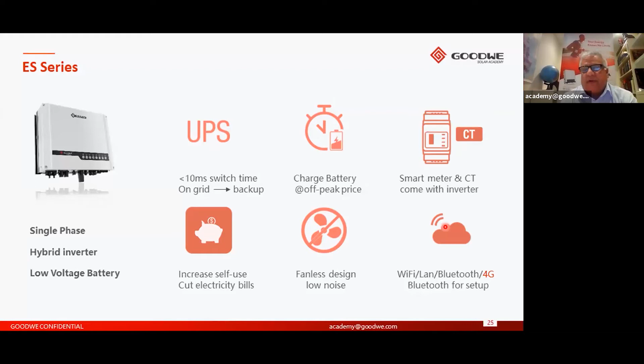This is important. Monitoring we do recommend for all of our products, not just for the grid-tied inverters, but also for the energy storage products. Through the portal on the energy storage products, you can see what you're generating from your regular PV curve. You can see what you're charging and discharging. You can see the state of charge of the battery. You can see what you're drawing from the grid. There's a lot of information. You can see what you're exporting as well. So by looking at your monitoring solution, you can configure your system so it works better for your customers.